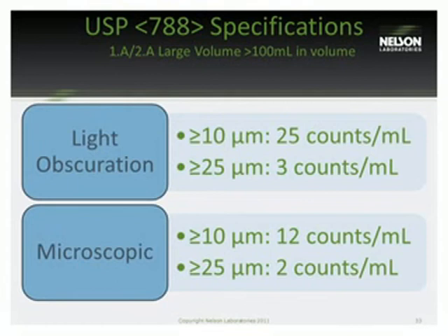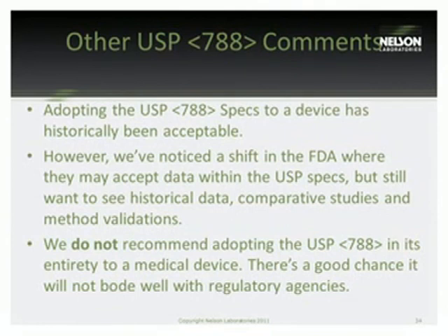Some other comments about the 788. Like I say, adopting the USP 788 to a device has historically been acceptable, but we have noticed this shift with the FDA, where they may accept data within the USP specification depending on your reviewer, but they still want to see historical data, comparative studies, and method validations. If you just simply present them with data that's below the small volume specification for the 788, I wouldn't expect to be able to just receive approval based on that alone.